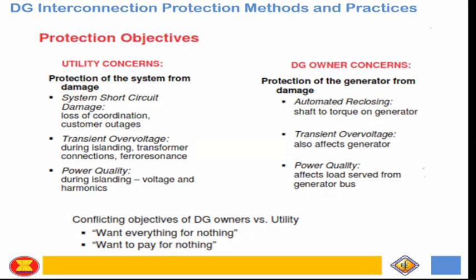And then the power quality affects the load served from the generator bus. Okay? As mentioned earlier, in one case the system is very unbalanced, and that also affects the capacity of the generator, because the unbalanced current also limits the negative sequence capability of the generator. So you will now have limited capacity because you need to consider the unbalanced current.